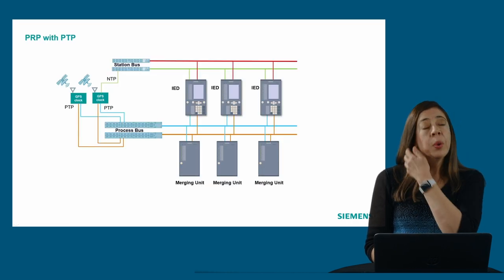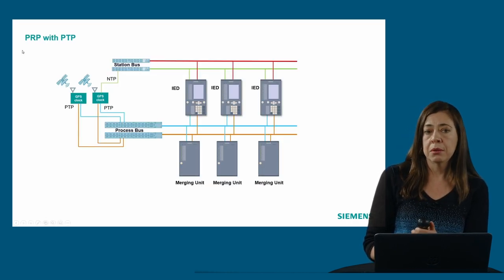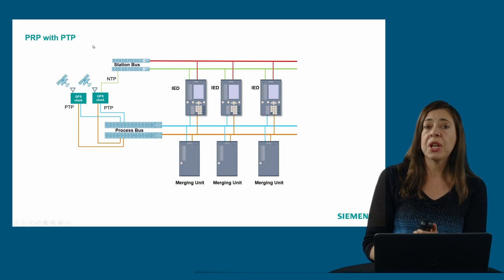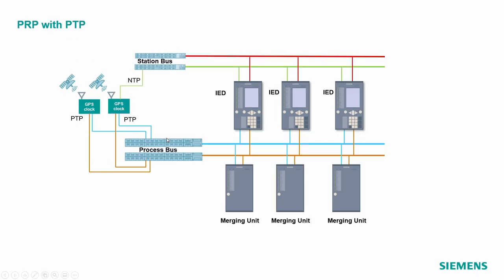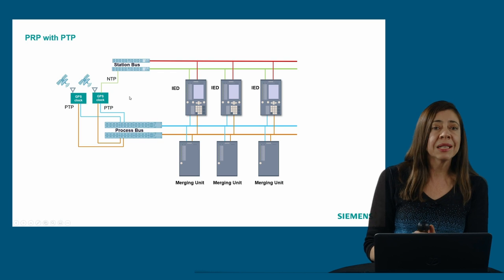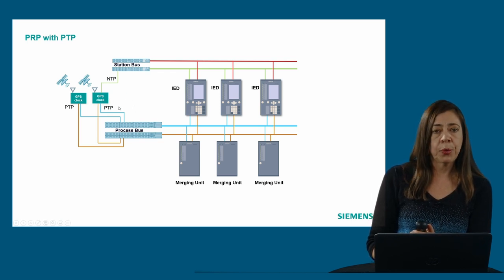We can also have PRP networks using the precision time protocol. So here we have for the process bus our two networks, PRP-A and PRP-B, and our master clocks redundant and also connected in a redundant manner to both networks. This configuration is important because in such a way we grant that the master clocks are seeing each other all the time and they can define by themselves who is the one giving the synchronization signal, meaning who is the one acting as the grand master clock in the network.